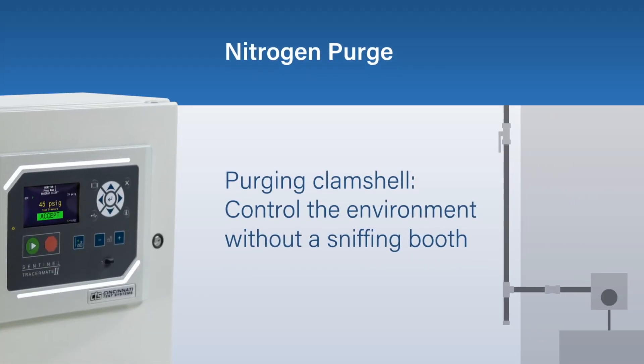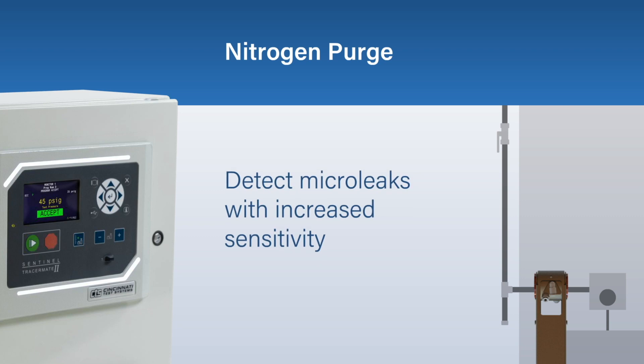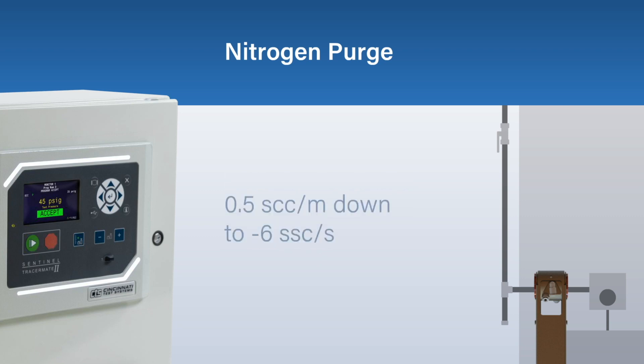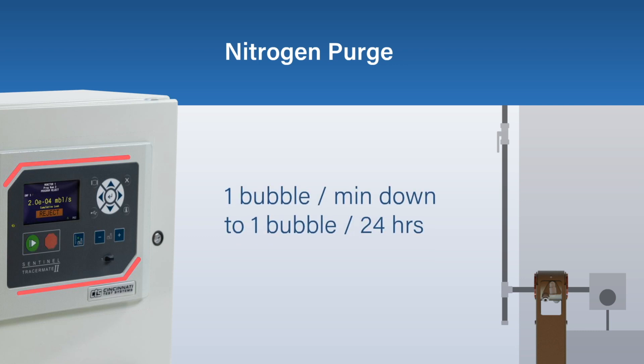The purging clamshell is a special device that can be clamped around a joint to close off and control the environment without a sniffing booth, so it can detect micro-leaks with increased sensitivity. This test method allows you to test critical areas of the part without having to enclose the whole part in a chamber.